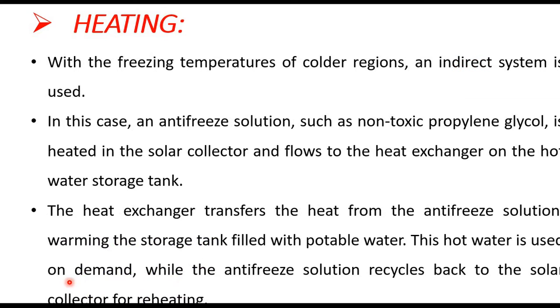Now, with the freezing temperature of the colder regions, an indirect system is used. In this case, an antifreeze solution such as non-toxic propylene glycol is heated in the solar collector and it flows to the heat exchanger on the hot water storage tank, and the heat exchanger transfers the heat from the antifreeze solution, warming the storage tank filled with potable water.